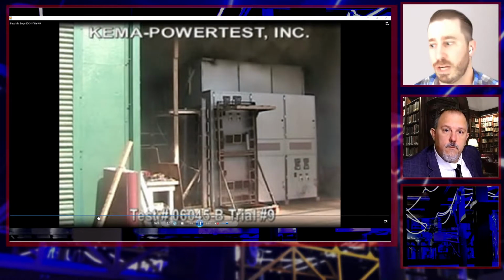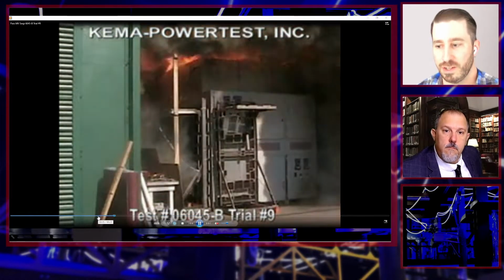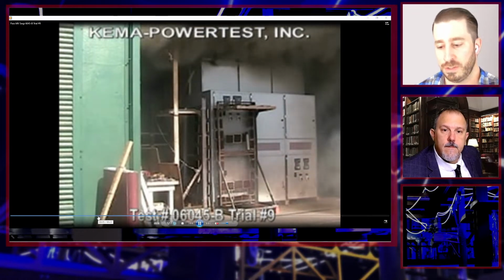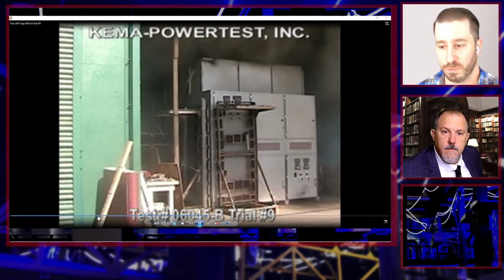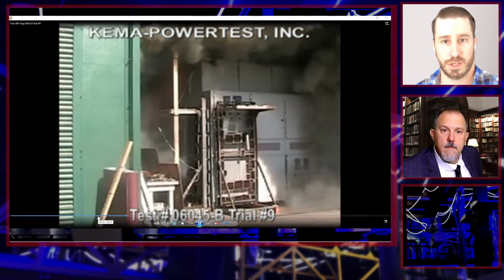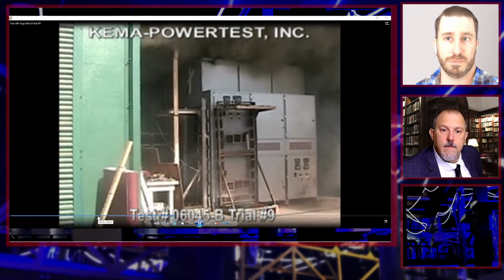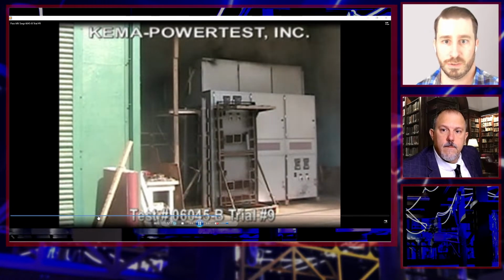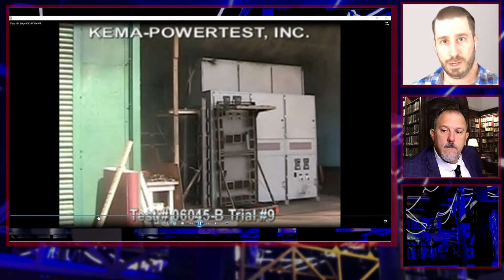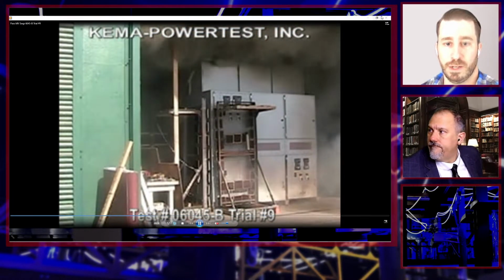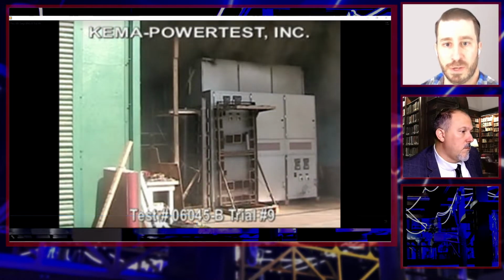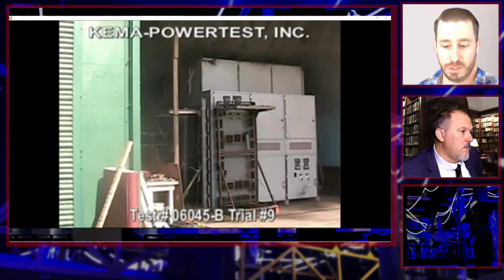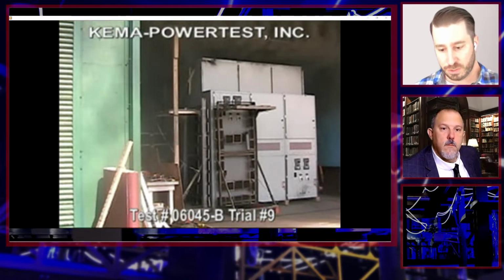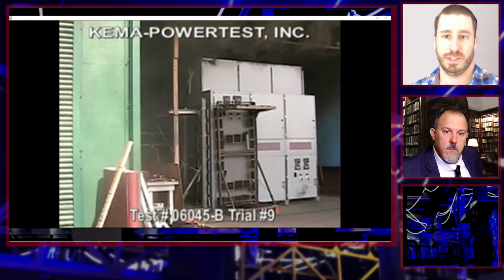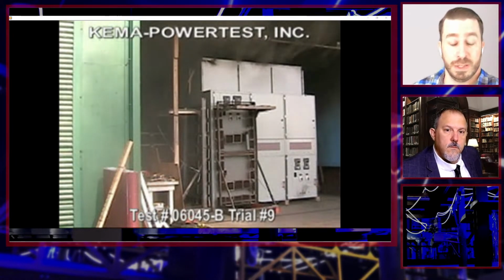It's one of the challenging parts when you get into such high voltage and duration, whether it's low voltage switchgear or medium voltage switchgear - there's so much energy built up. More commonly, what you'll find in arc resistant switchgear is a lot of need to vent and deal with the rapid pressure buildup in the equipment. It's something that has to be considered in the design. You've got a balancing act - you've got to make the structure strong enough to hold it back, but that obviously redirects that energy somewhere, so it has to be dealt with.